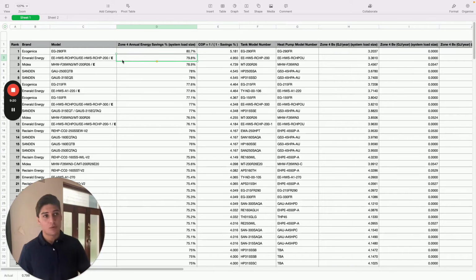These systems that come with boosters, the boosters are not actually designed to heat up the entire system. You'll be paying a lot of money to heat up the system, and the heat is not going to stay very well. So you're going to be using a 1.8 kilowatt booster to heat up a hot water system. It's not going to work after the element's gone. It's going to keep your water just warm at best. So the booster is actually not as good as it seems. It's also going to make your system more expensive.